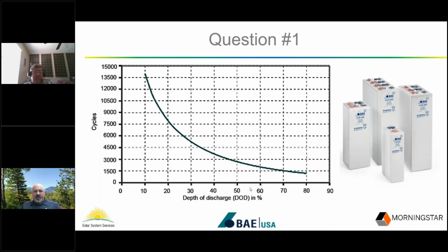It's questionable that any battery can be used at 100%, because if you think about it, at 100% you're going to have voltage collapse of your DC system, whether it's a lead acid battery or something else. So I wanted to point that out so people understand that when looking at rating sheets from a reputable manufacturer like BAE, the data given is the usable capacity.